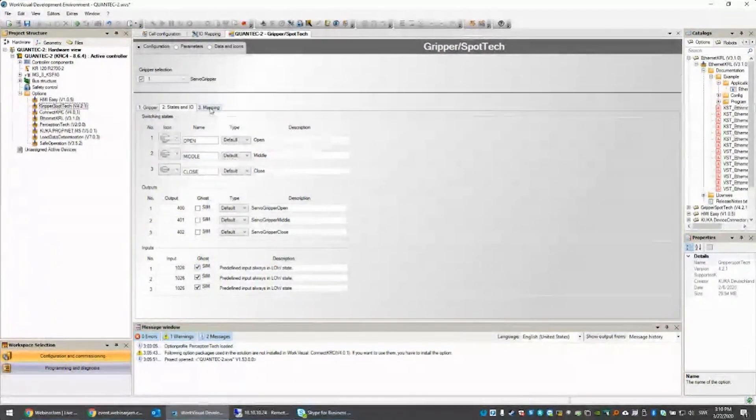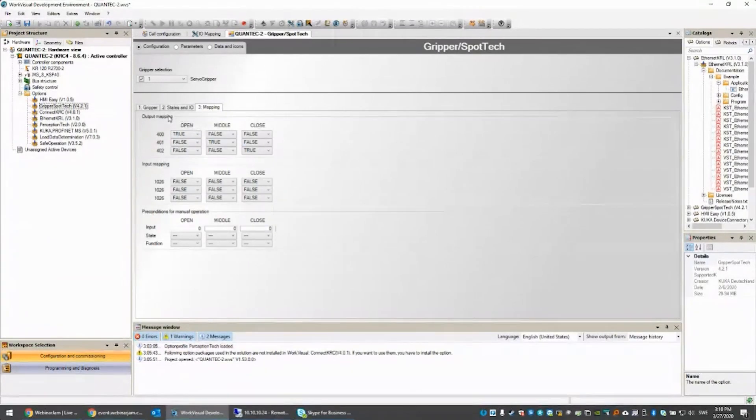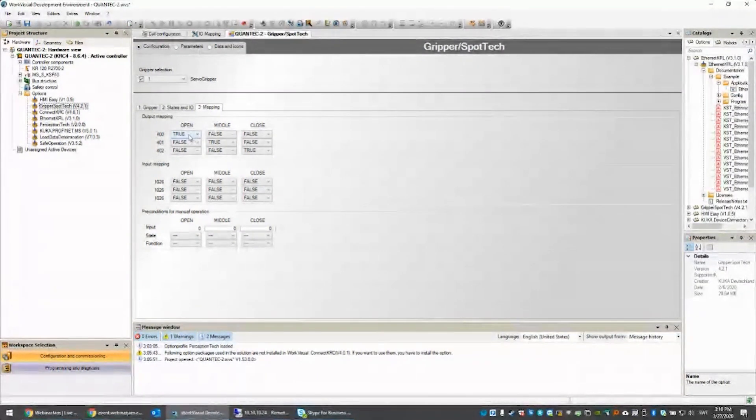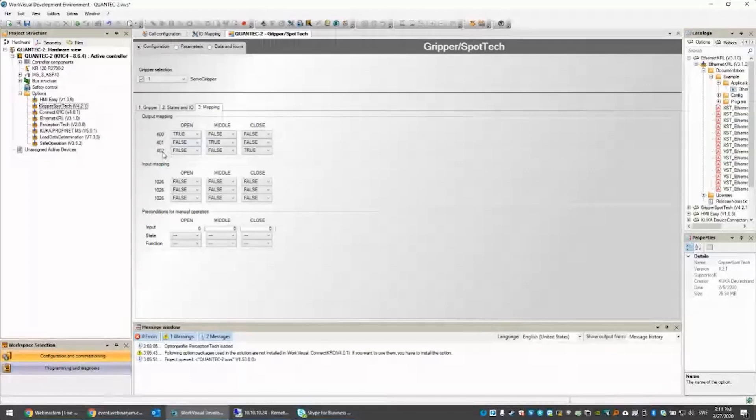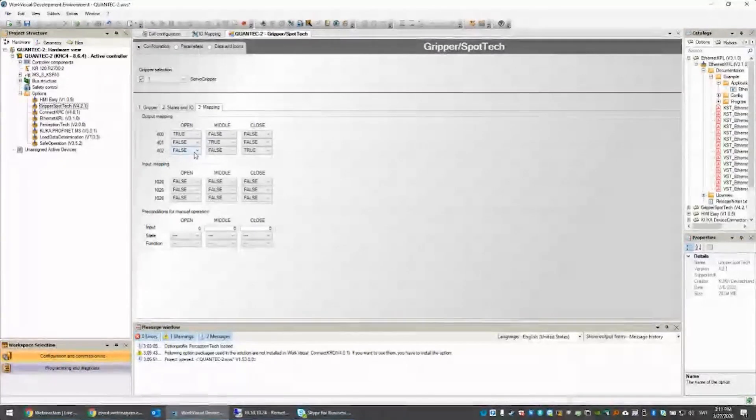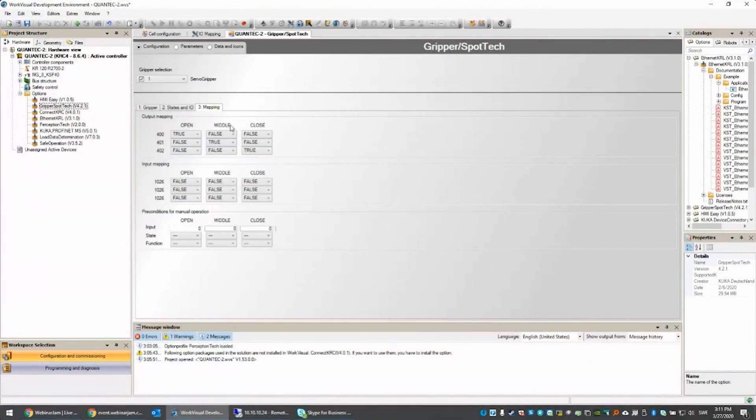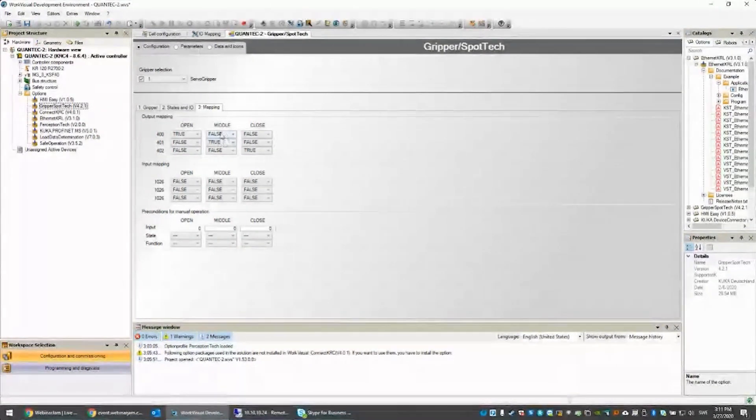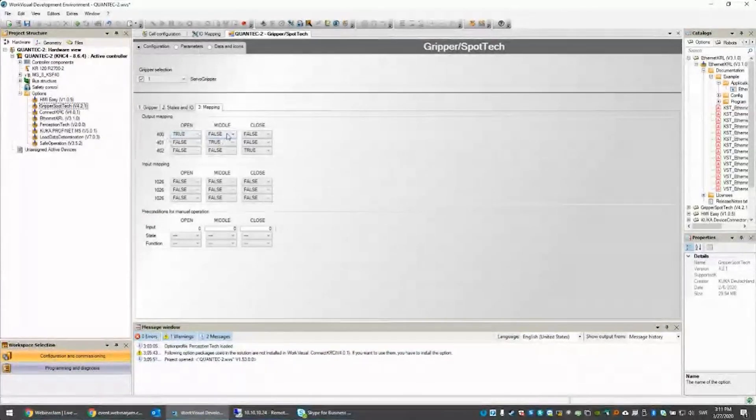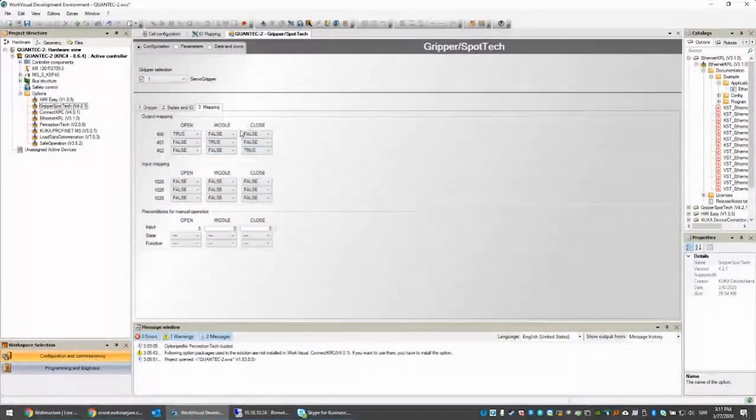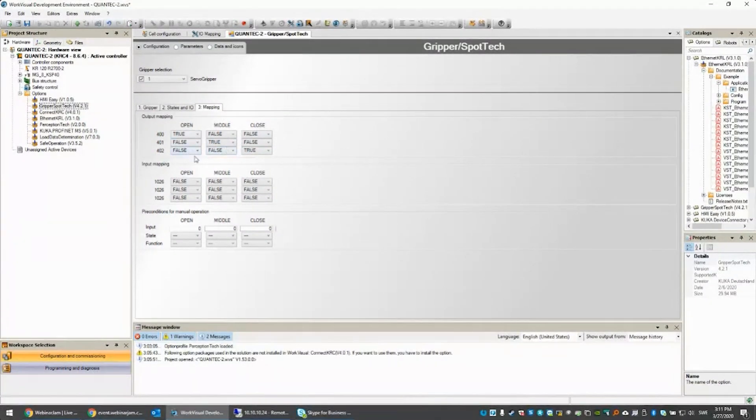The next tab is the output mapping. If I push the open state, then I want the signal output 400 to be high, 401 to be low, and 402 to be low. For the middle position, I want output 400 to be low, 401 to be high, and 402 to be low. That's how you build up your functions.